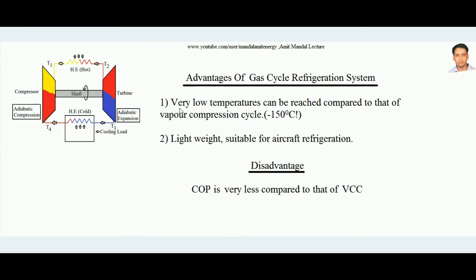Advantages of the gas cycle refrigeration system: First, since there is no phase change in the cycle, air remains in gaseous form throughout, and therefore it can attain very low temperatures — as low as minus 150 degrees centigrade. Second, since air is used as the refrigerant, the system is lightweight and suitable for aircraft refrigeration, where minimum weight is critical. The main disadvantage is that the coefficient of performance (COP) of this system is very low compared to the vapor compression cycle.